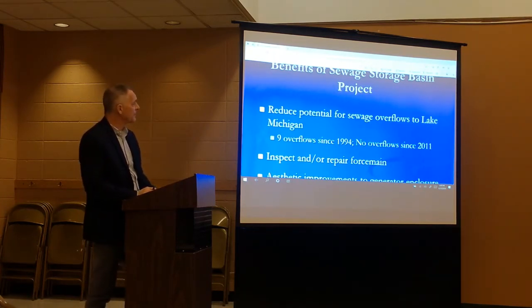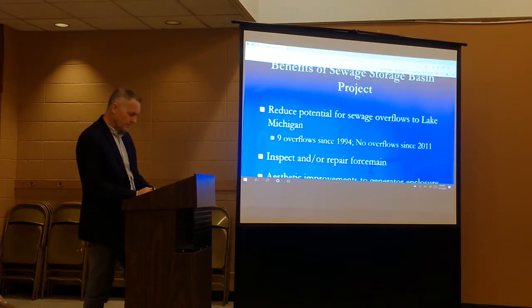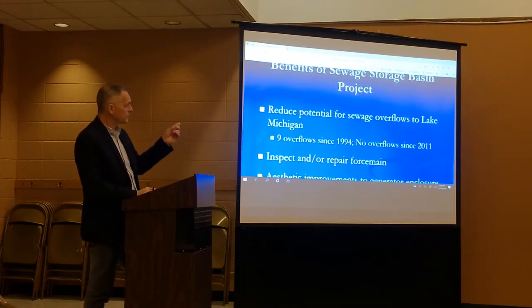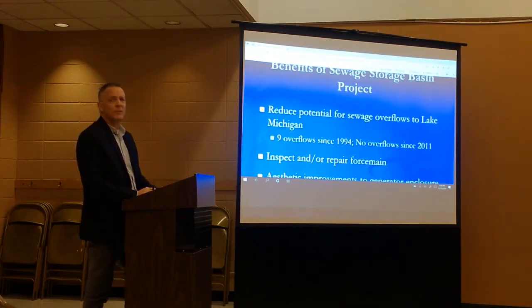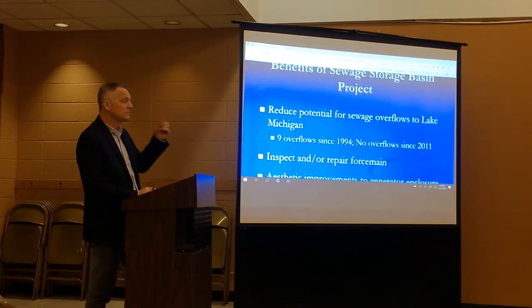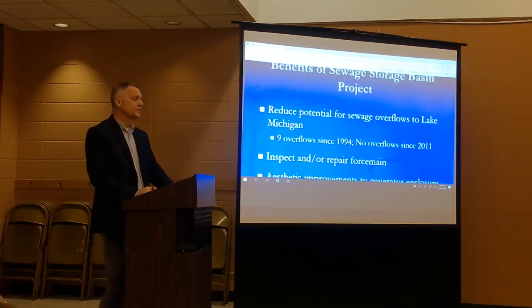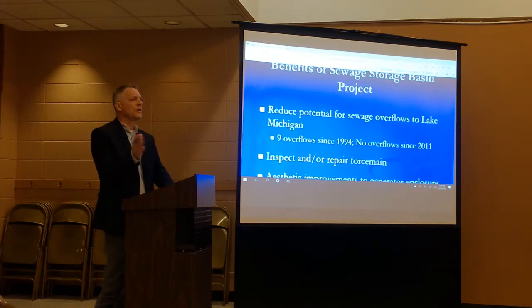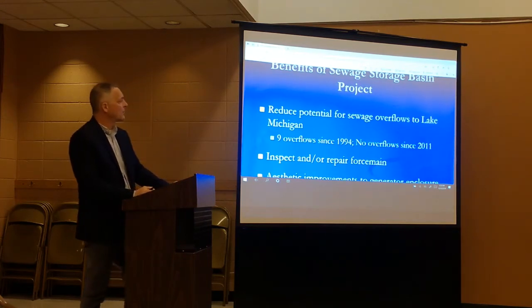We did have an overflow in September of 2018, and I think every one of these overflows except one was due to the loss of power from ComEd. In the most recent situation, our generator started, but there was a mechanical issue with the automatic transfer switch that transfers the station load from ComEd to our facility. We're actually in the process of upgrading that to more current technology.